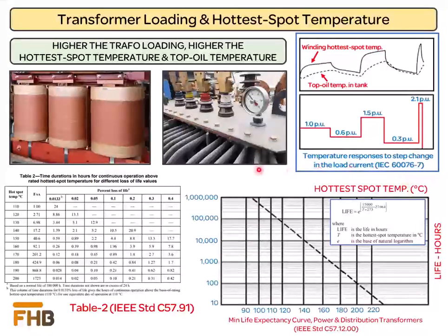IEEE standard C57.12.00 defines the relationship between transformer life and the hottest spot temperature of the transformer. The life of 180,000 hours is estimated at the hotspot temperature limit of 110 degrees centigrade. If the transformer is operated above 110 degrees centigrade, the life of the transformer is drastically affected. The same is also defined in IEEE standard C57.91 under table 2. For 24 hours of operation of the transformer at 110 degrees centigrade, the loss of life is estimated at 0.0133%.